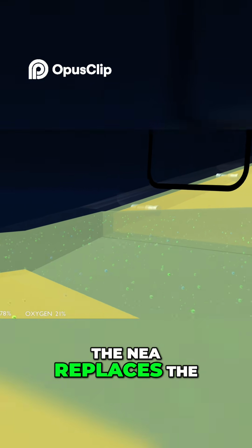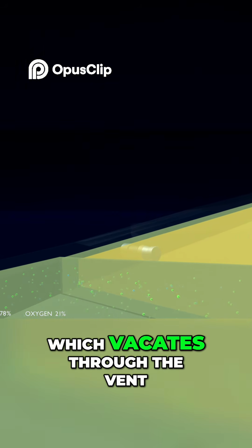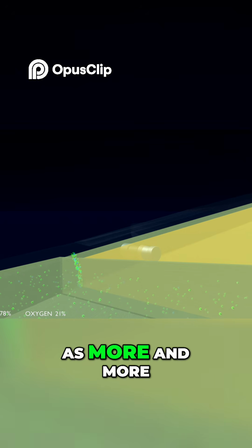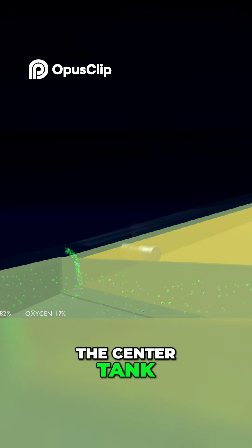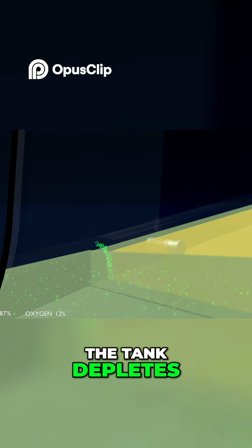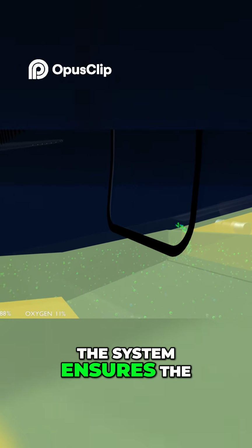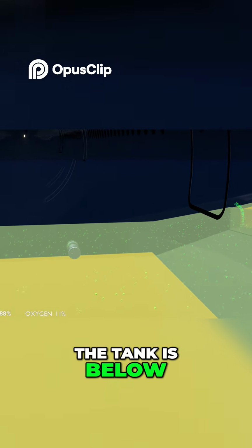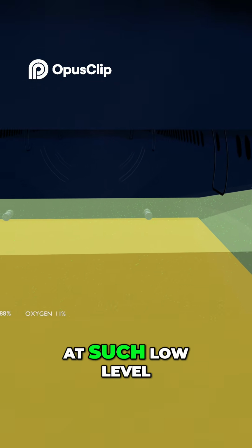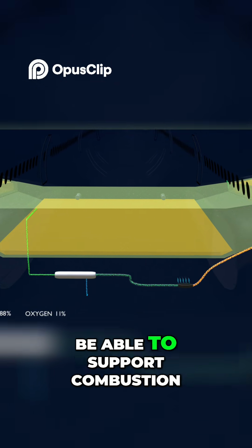The nitrogen-enriched air replaces the air within the tank, which vacates through the vent. As more and more nitrogen is pumped into the center tank, the oxygen level inside the tank depletes. The system ensures the level of oxygen in the tank is below 12%. At such a low level, the oxygen will not be able to support combustion.